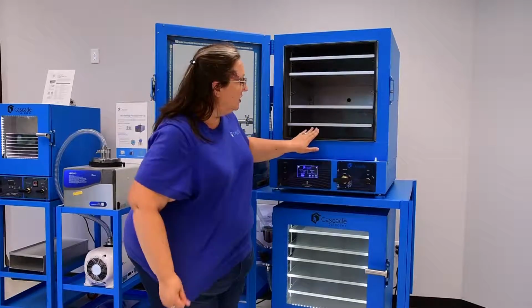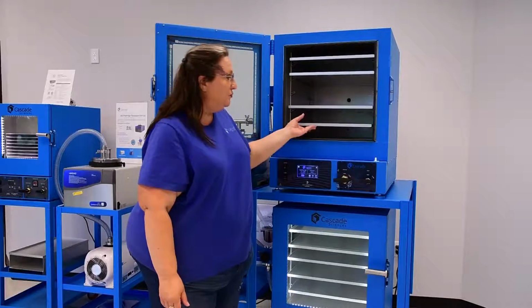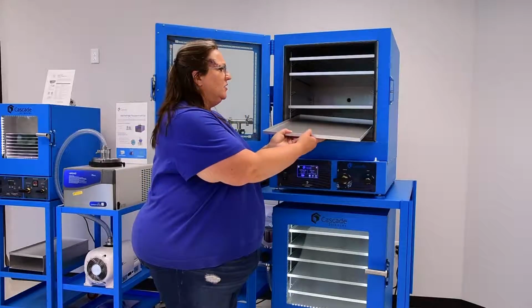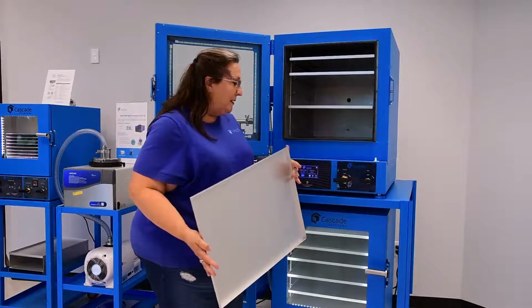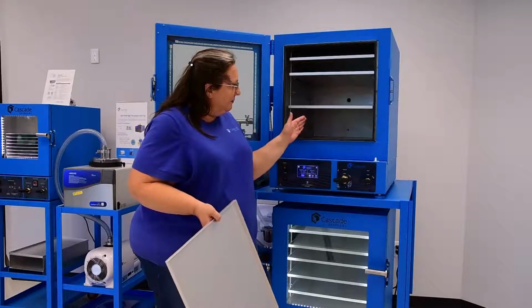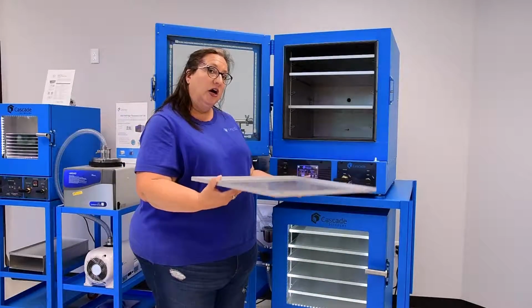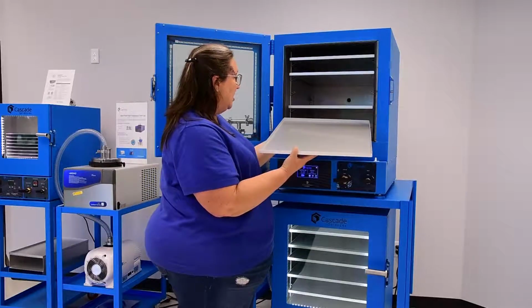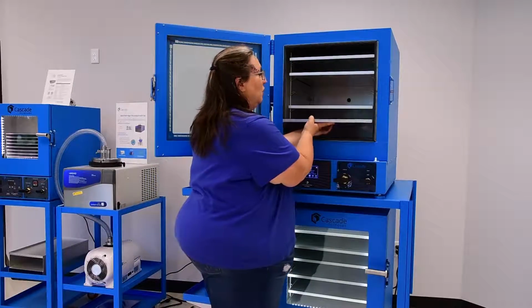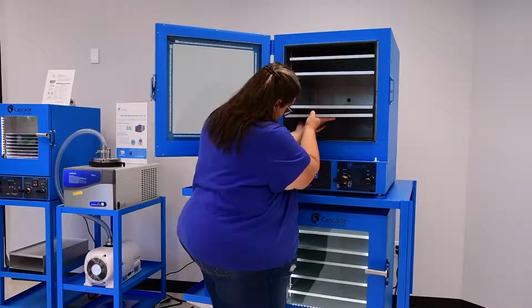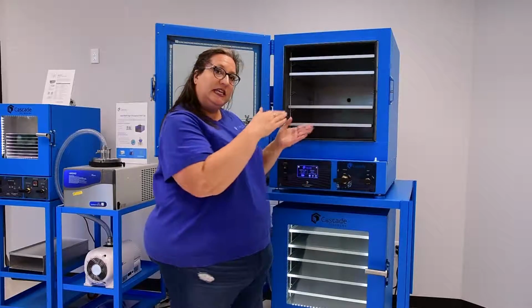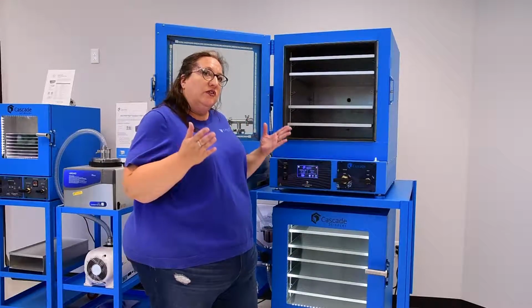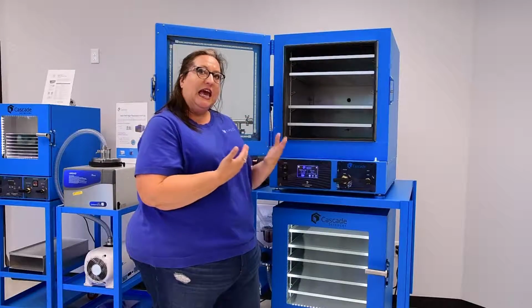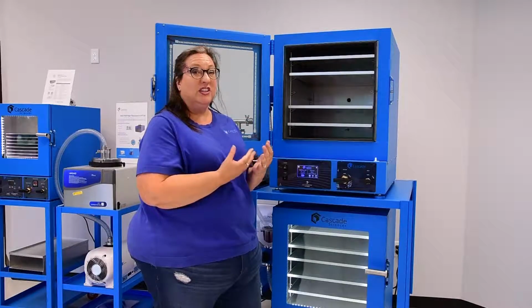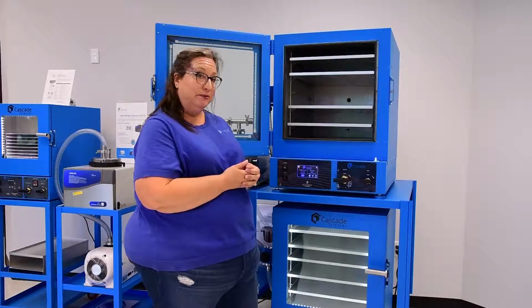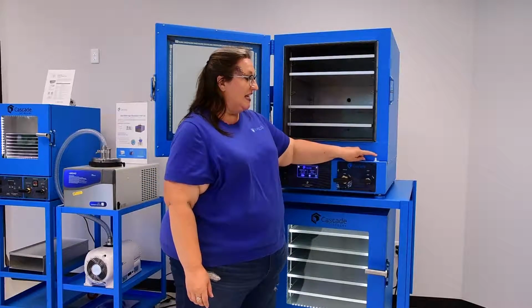If you look down real close, you're going to see that we have a temperature probe that extends quite a ways into the oven, about 6 inches. That temperature probe extends into the oven, and part of our design is putting the bottom shelf right above it. What this does is reflect heat down to the probe so that the probe sees heat in the absence of circulating air, where it's really difficult to conduct temperature. This is another fantastic feature.